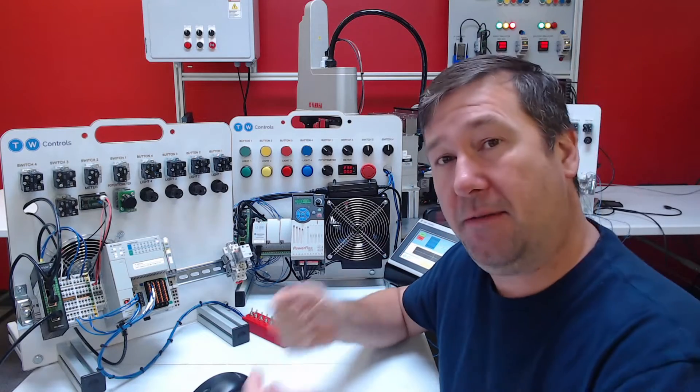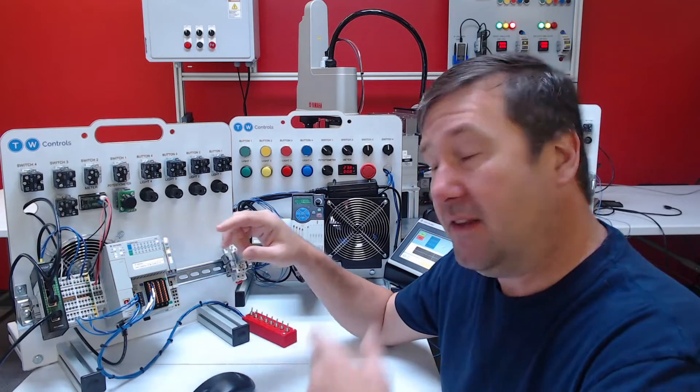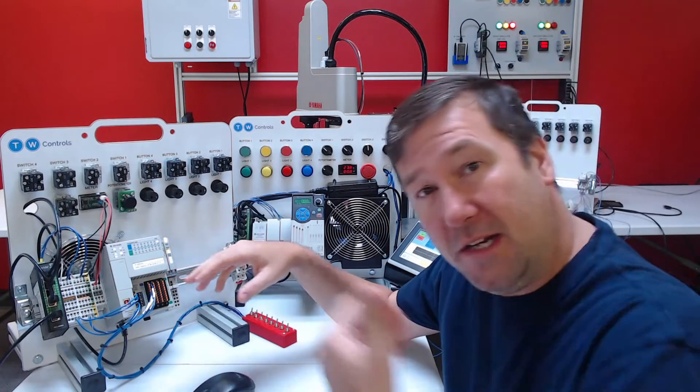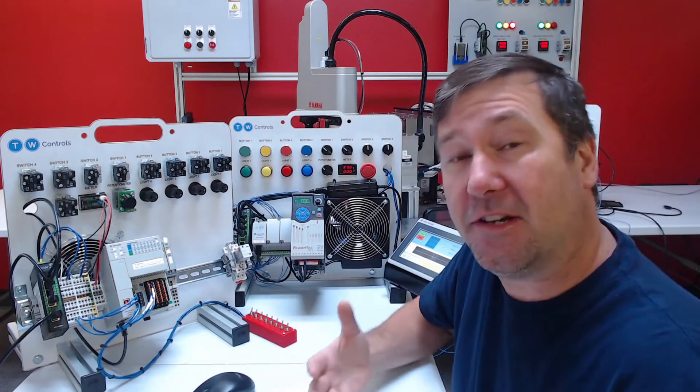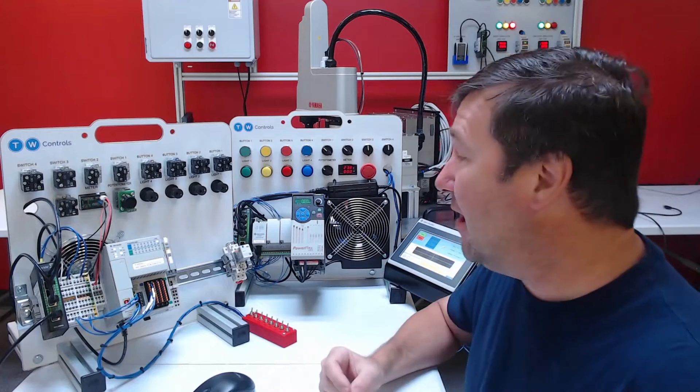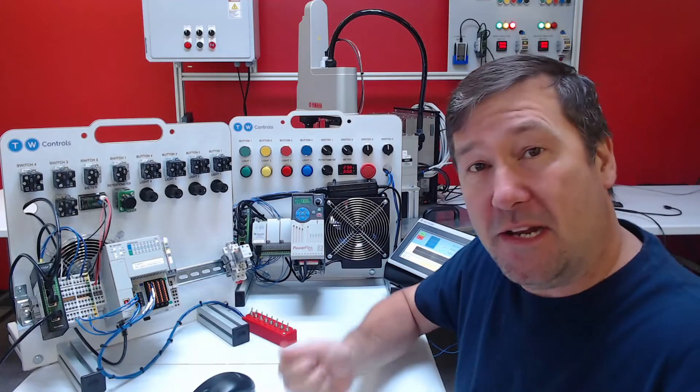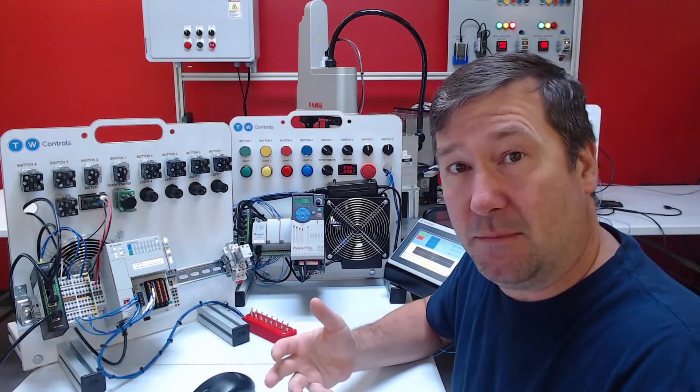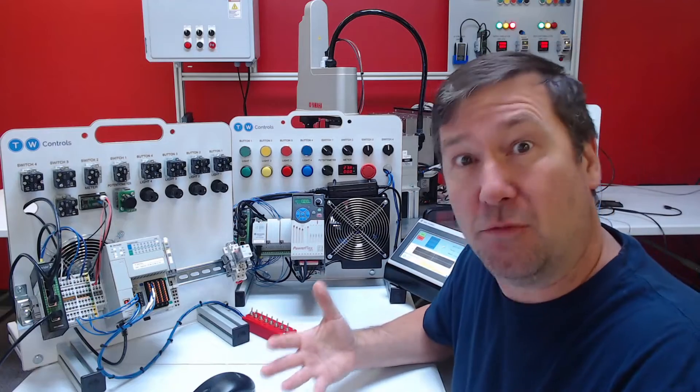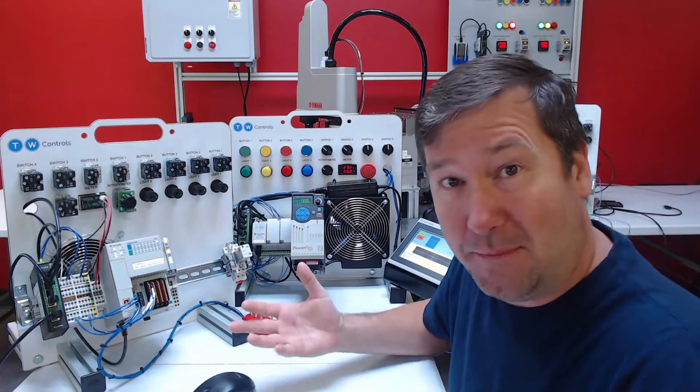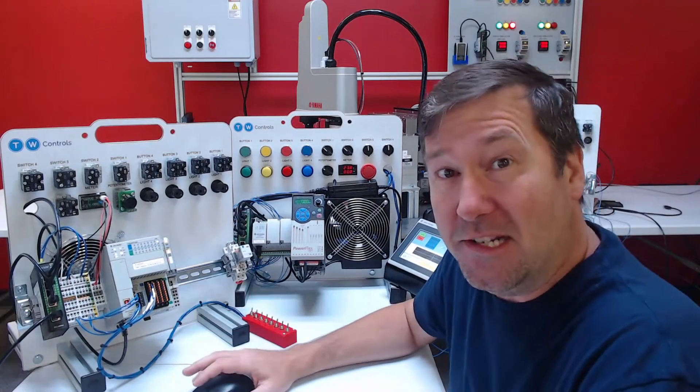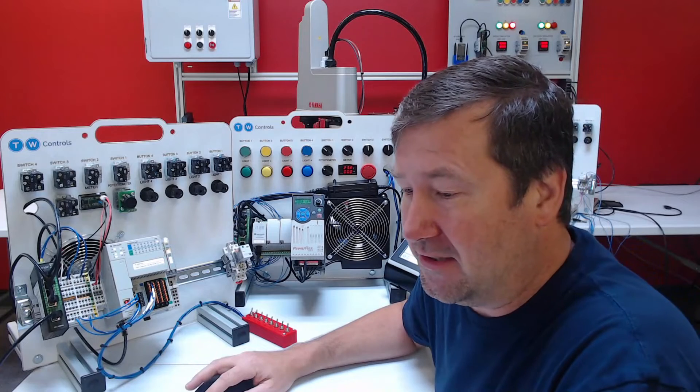But what I say is, if you have a list of numbers that somebody has given you that you need to read from a PLC, then you're going to need a Modbus client. If you need to create those Modbus numbers for somebody to read, then you need to create a Modbus server. So in this case, we are going to create a server.